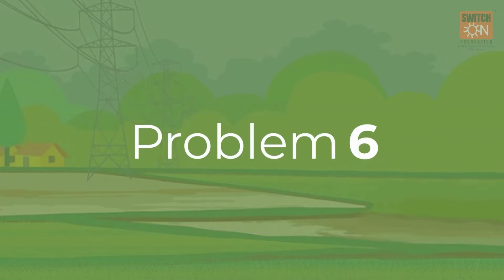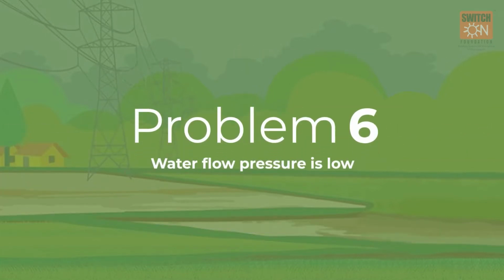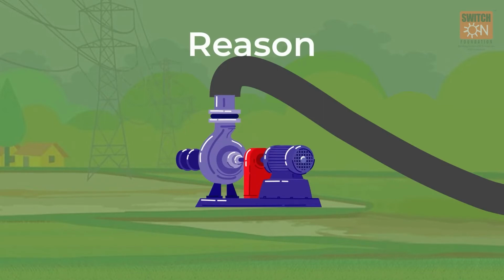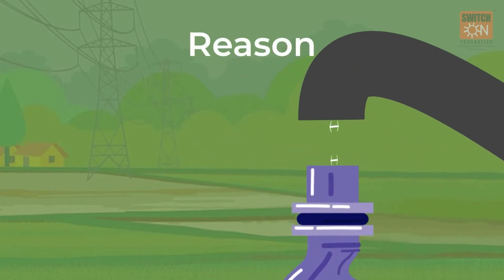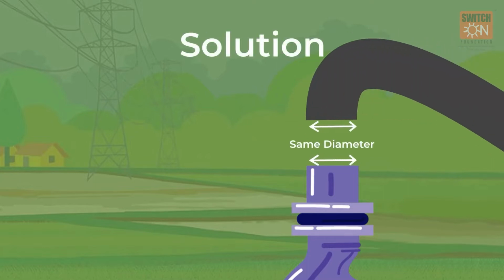Problem 6. Water flow pressure is low. Reason: the delivery pipe diameter is larger than the pump output pipe diameter or nozzle diameter. Solution: use a delivery pipe of the same diameter as the output pipe or nozzle.